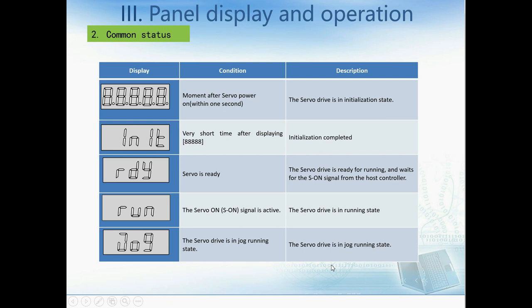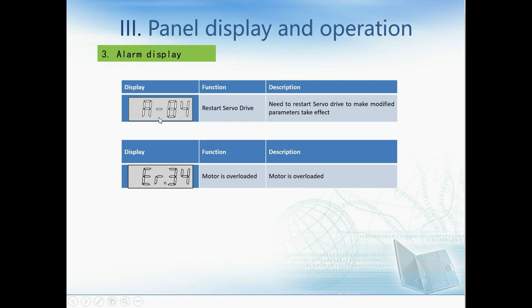Here are two alarm displays. The first is 'A-84', which means we need to restart the drive for modified parameters to take effect. And error 34 means the motor is overloaded.